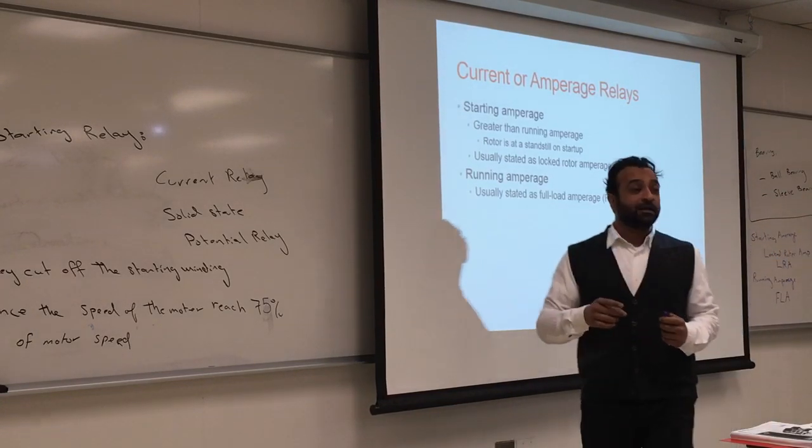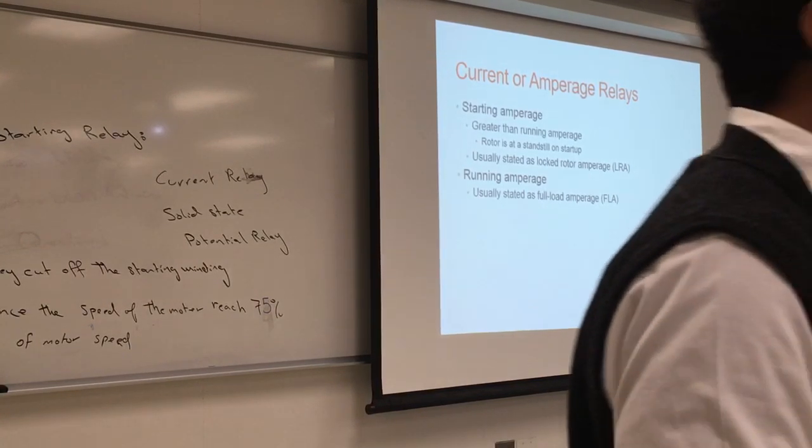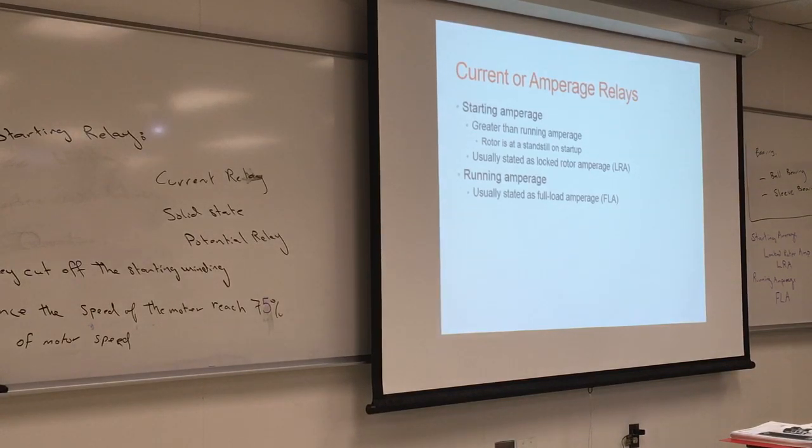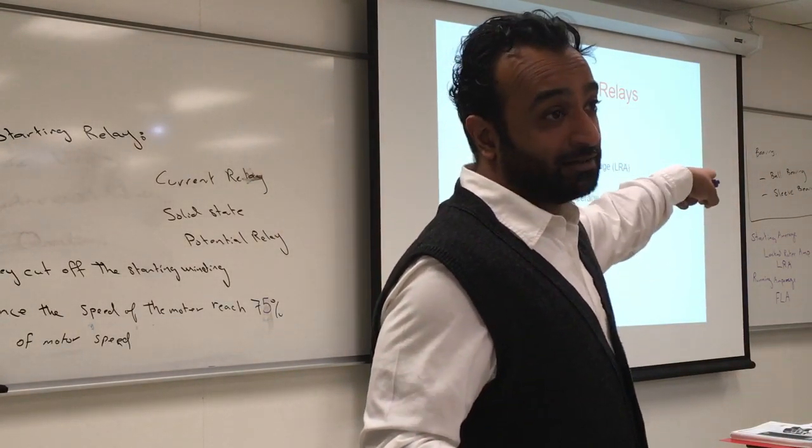Full load amperage. What is full load amperage? Again, in the lab, do you notice that the motor has a full load amperage. It's like what is the amperage supposed to be drawing when it's running. And when we run the motor by itself, it was less than the label. Why? No load. No load. Whether it being a fan, whether it being a weight, whether it being a motor. So it's designed to run something at this full load amperage. So when you run it by itself with nothing on the shaft, it's going to be a little bit lower. When you put your inducer fan motor, when you put your pump, it's going to be a little bit higher. Then if you hook up everything, it should be around that full load amperage. It should not be higher.